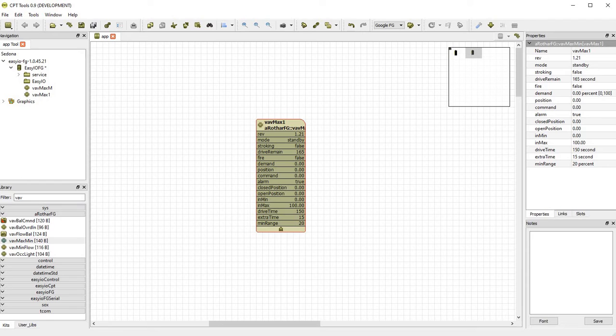So our maxmin commands were actually devised to control VAV actuators. A lot of VAVs don't stroke the full 90 degrees or the available range of the actuator, so their open and closed positions aren't 2 and 10 volts.